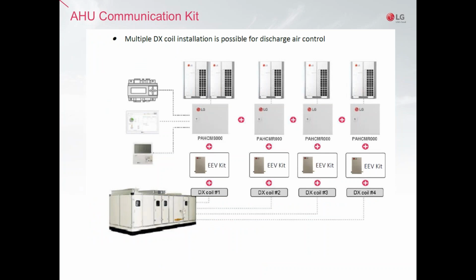Talking about configurations when you have multiple EV kits connected to the same air handling unit. This is an example of how to achieve a very large ton capacity with multiple EV kits and condenser units in supply discharge air temperature control. If you remember, the supply air temperature control is the only one that can use the large EV kit, but it has a limit of a maximum of 4 EV kits that can be connected to a single air handler, which can give you a potential maximum capacity for a DOAS MUA of 594,000 BTUs multiplied by 4, like in this drawing.